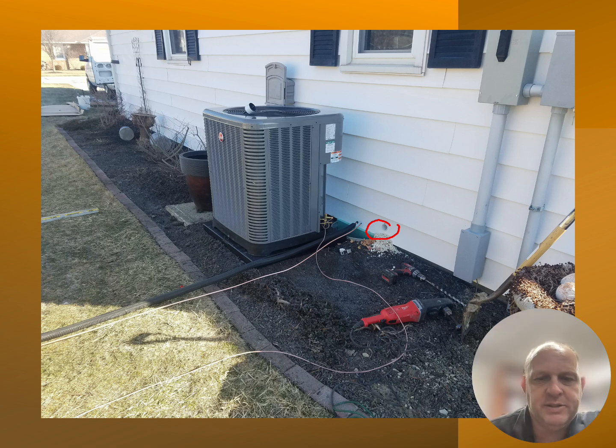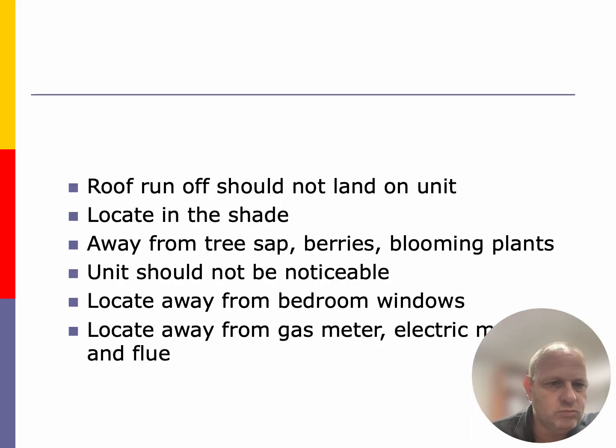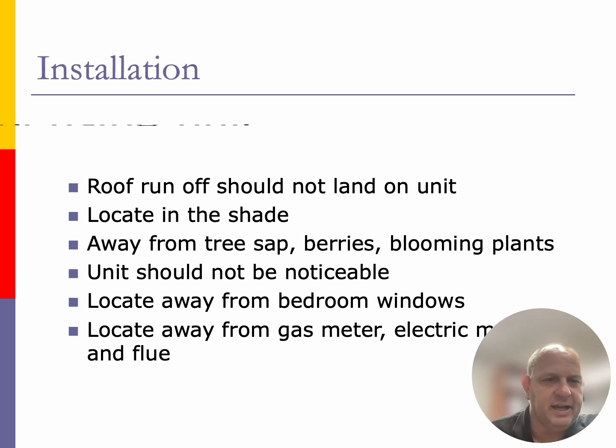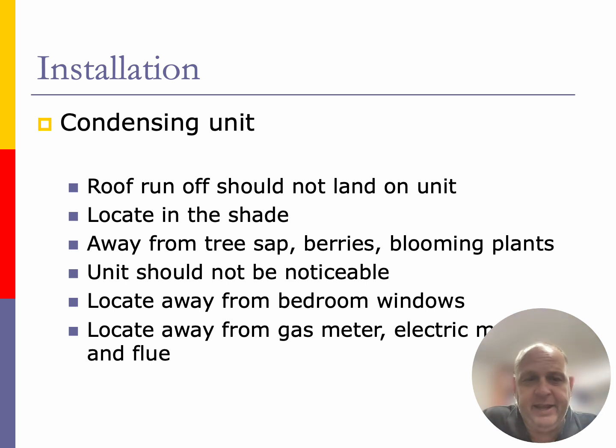As far as the condensing unit and the installation of it, we're going to be looking at runoff from the roof. Should not land on the unit. Locate in the shade. Better for heat transfer if the sun's not beating on that guy. Away from tree sap, berries, blooming plants, and these things are going to grow up inside of that particular unit itself. Units should not be noticeable. That's why individuals like to put shrubs around it, but it's kind of avoidable, not avoidable now because of the size of these units. Located away from bedroom windows, located away from gas meters, 5 feet, electric meters, 5 feet, and the flue gas coming out from the unit at least 5 feet is what we're looking at for that particular unit.